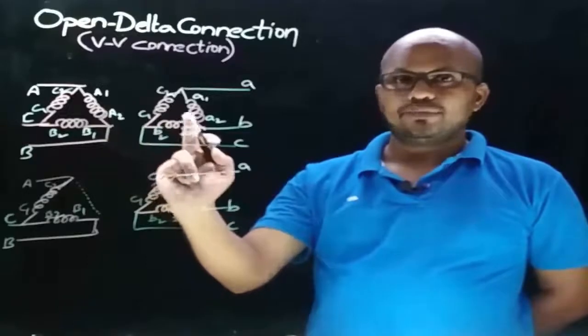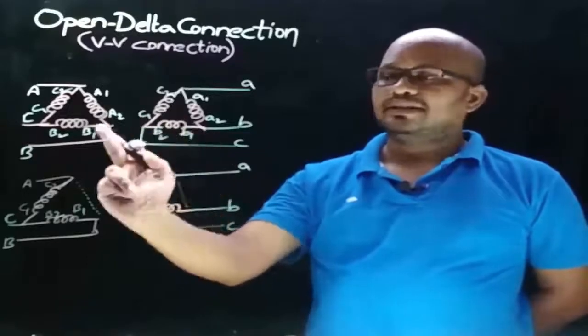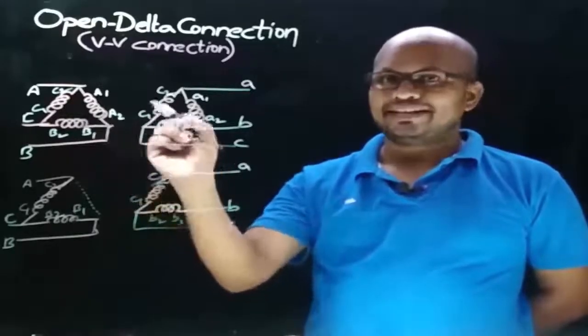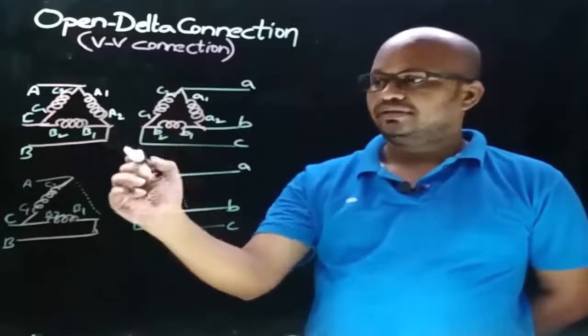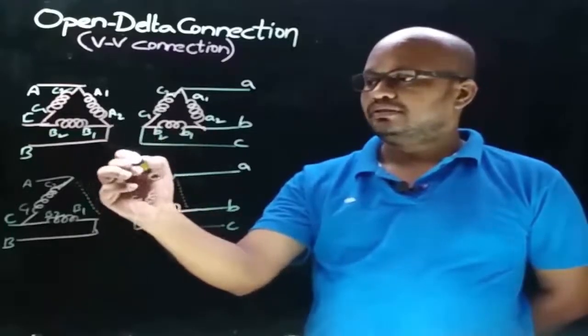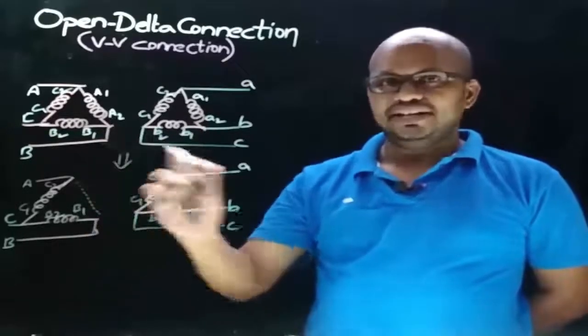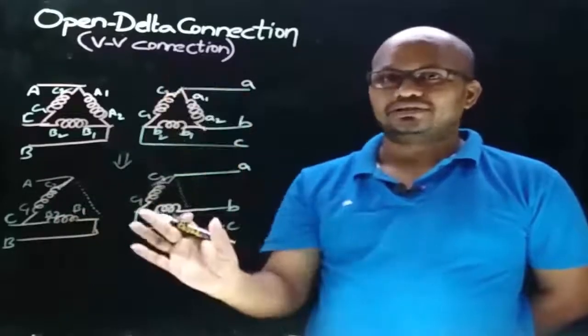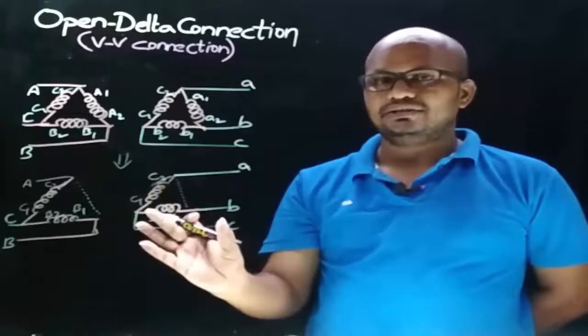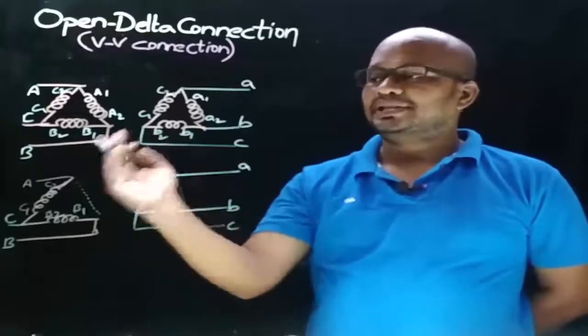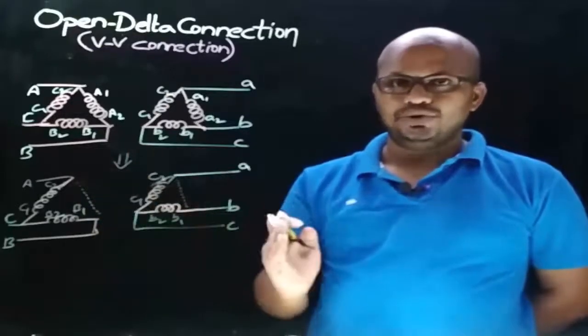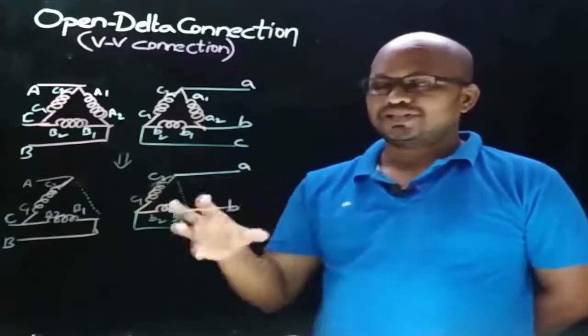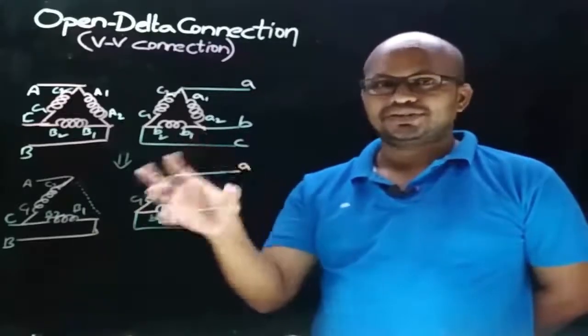So when one of the transformers in a delta-delta connected single-phase three-transformer bank gets failed, the resultant winding connection is called open delta connection. With this open delta connection, we can maintain the continuous supply to the load but with reduced capacity. Now let's determine the reduced capacity.